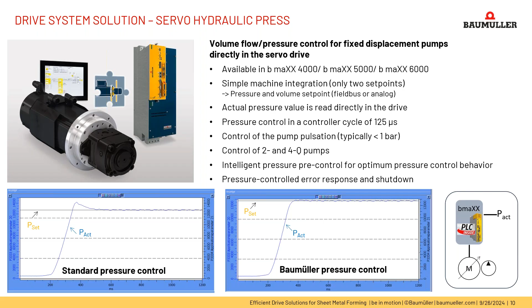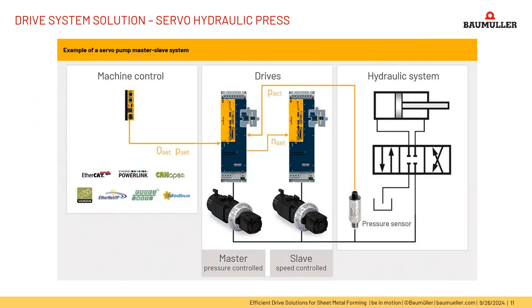Servo hydraulic presses typically require high flow volumes. To provide this very demanding high performance requirement, it is common to have a master and slave configuration as shown here. In this example, the set values provided by the machine control are read in and processed over the fieldbus by the master drive. The control and integration of additional slave drives is carried out by our drives internally without the need for an additional controller.